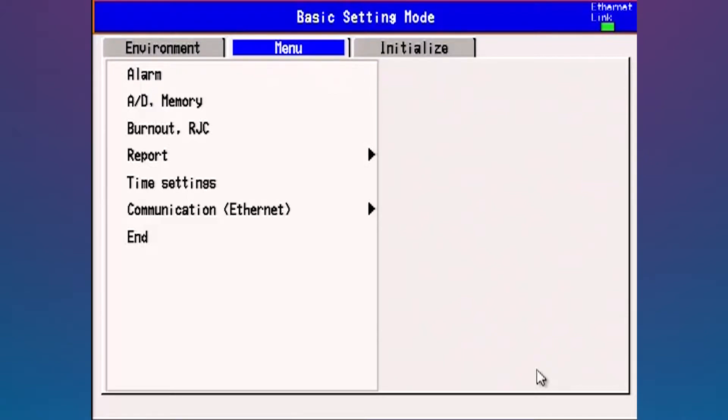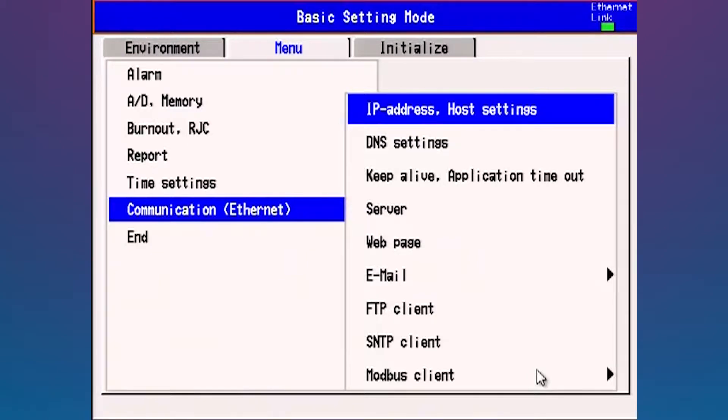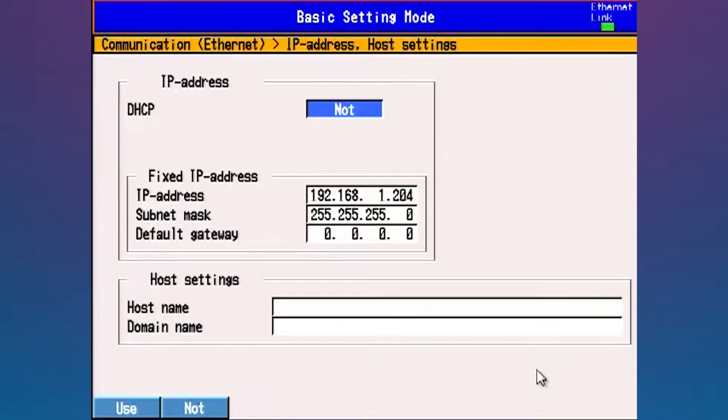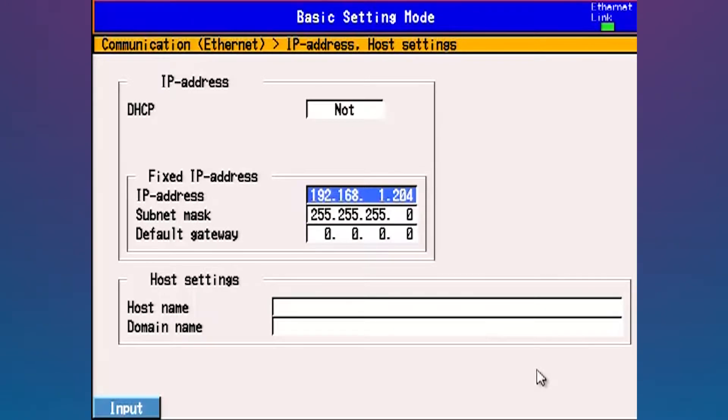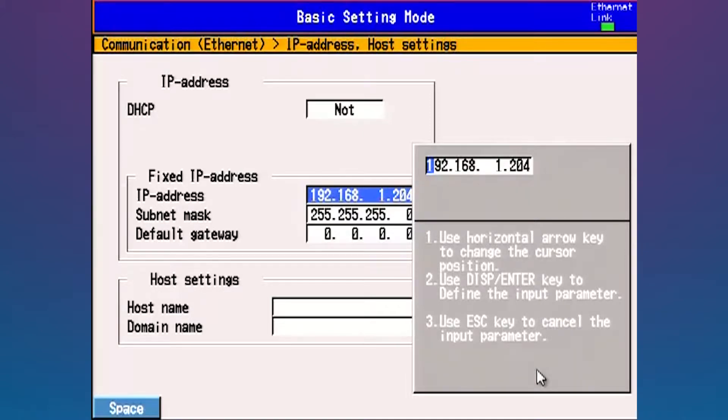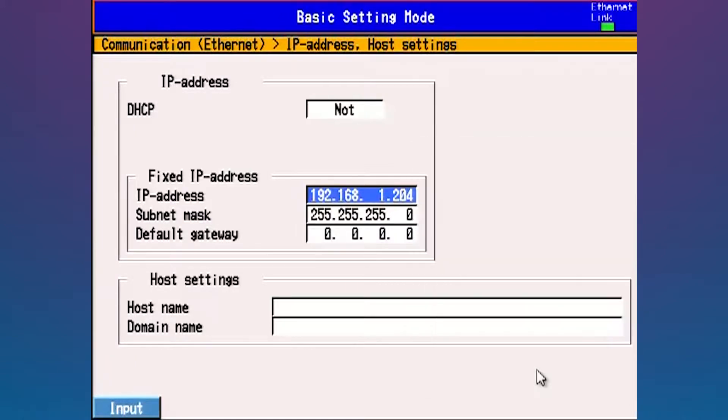I'm going to enter basic setting mode. As far as configuring remote communications, everything is done under the menu communication ethernet. The first thing we need to make sure is set up is an IP address. This is your network address that your MV Advanced should have on your network. I've set mine to 192.168.1.204 and I've set a subnet mask of 255.255.255.0.